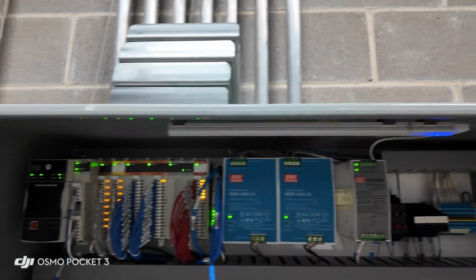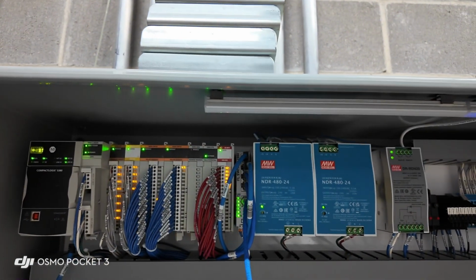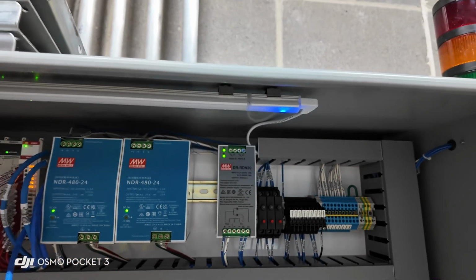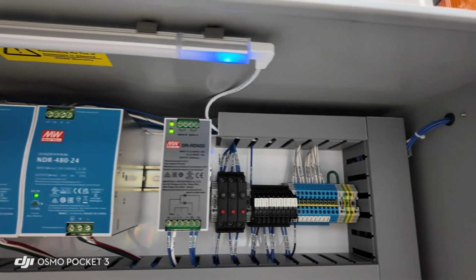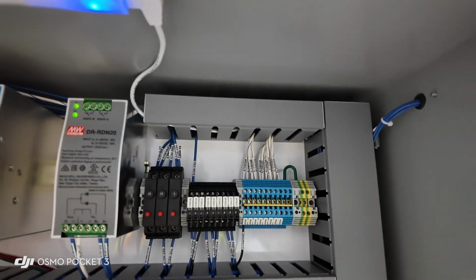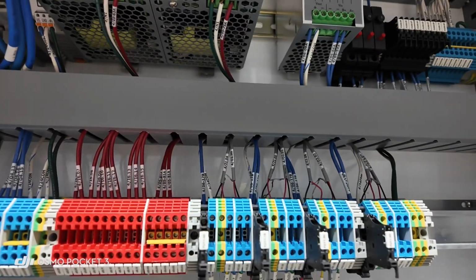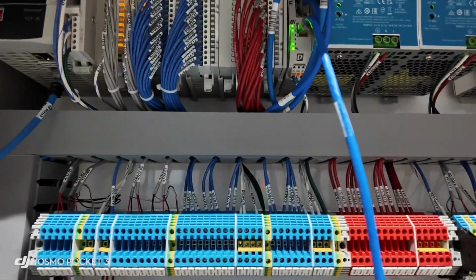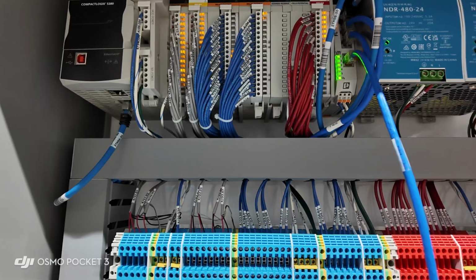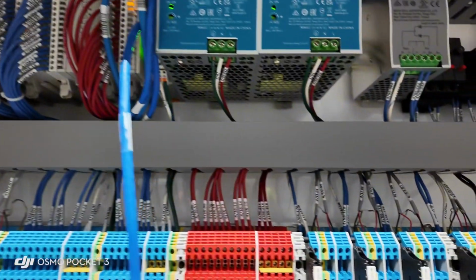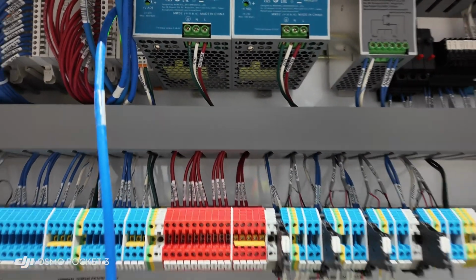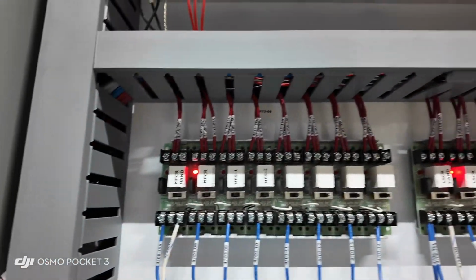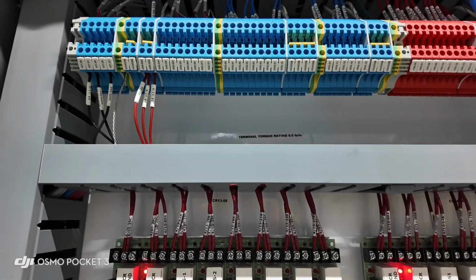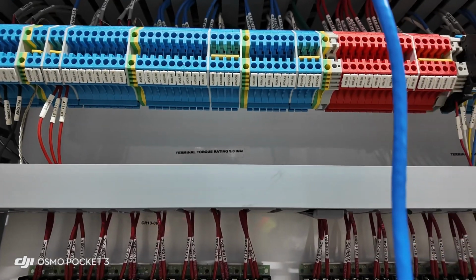Okay. As you can see through the panel here, we have PLC rack, redundant power supplies, Ethernet switch. We then have a power supply monitor, again, crossover, breakers, fuses, lighted indicated fuses. We have analog input fuses, and the blue wire indicates that it is 24 volt DC. Red wire is 110 volt DC. As you can see on those cards, we bring in 24 volt DC outputs through the relay card, switching over to 110 volt to solenoids.